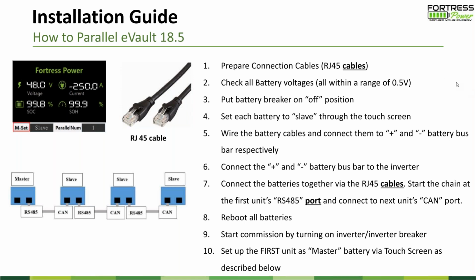And after you turn on the inverter, then you can change the first battery to master. What will happen is once battery 1 becomes master, it starts to coordinate with all the other batteries to make sure the whole system is in the same voltage range, and then starts supplying power to the inverter. It's extremely useful when you are commissioning a big system. If you have 5, 10, that's the way you want to do it. You don't have to calculate everything to 0.5 volts and so on. And the system will help you understand if this battery is in the range of a parallel system or not. We have detailed instructions in the user manual. You can go online to www.thefortresspower.com resources. You can download the guideline and the installation manual that have detailed instructions for these processes. Okay, next slide, please.